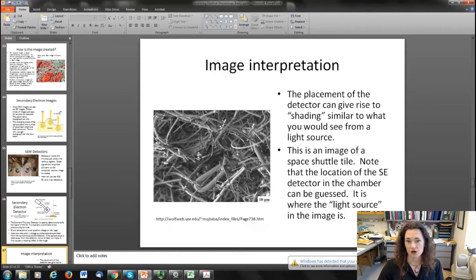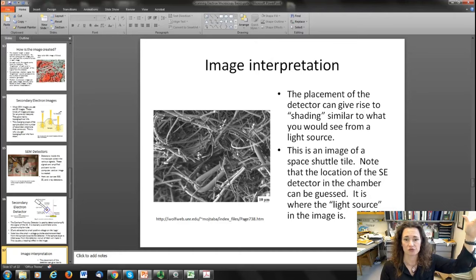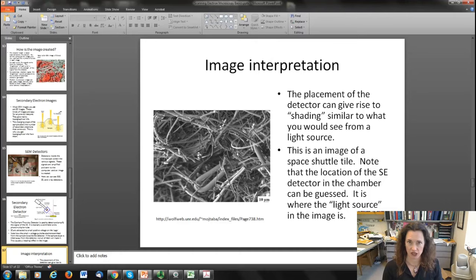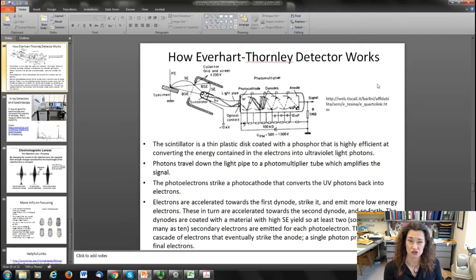The placement of the detector inside the chamber is something any good SEM operator should remember. It looks like a light source from a typical black and white image, so when you look at an image of shuttle tiles, for example, your brain interprets a sun or light source on one side and shadows on the other. What it really means in a secondary electron image is that the detector is over there. The scintillator itself is basically a thin plastic disk coated with phosphorescent material that efficiently converts the energy of electrons into ultraviolet light photons, and those photons travel down a light pipe to a photomultiplier tube.